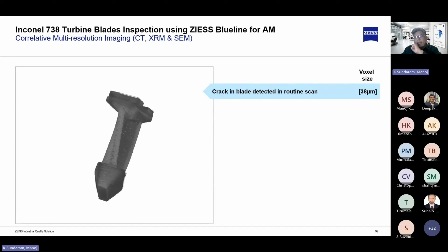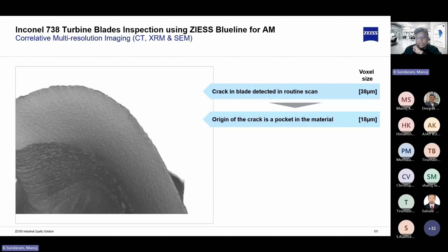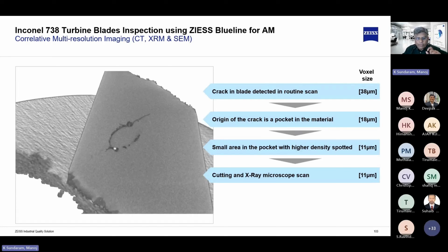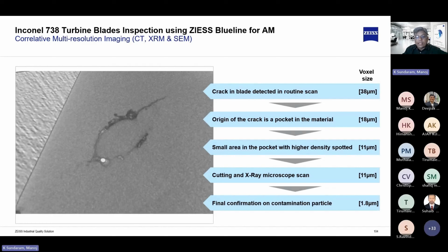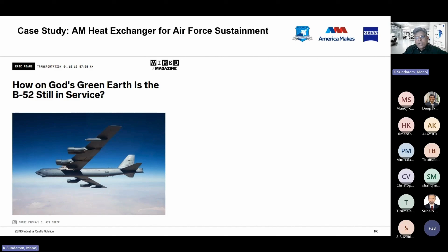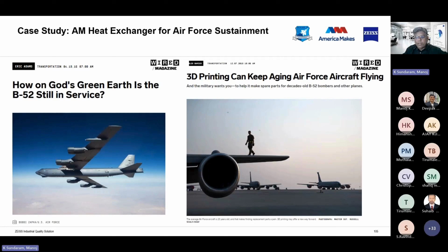You do a CT, then you look at that and see there is a crack at a certain location. Can I do a finer measurement at 18 microns? Oh, now I see it in a little more detail. Can I get a little higher resolution to see what is going on there? Then I go down to 11 microns. Fine, good enough. Now, can I cut it and put it in an X-ray? Why has it cracked? What you see here now is a highlight, a material with a white spot. That white spot is a foreign body which has come in there. So for that foreign body, we will have to confirm what the contamination particle is in a microscope, as Mr. Parani explained in his presentation.